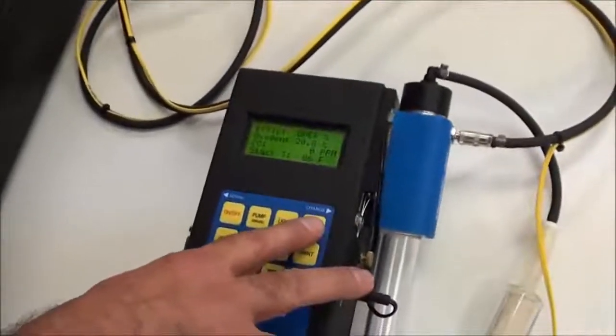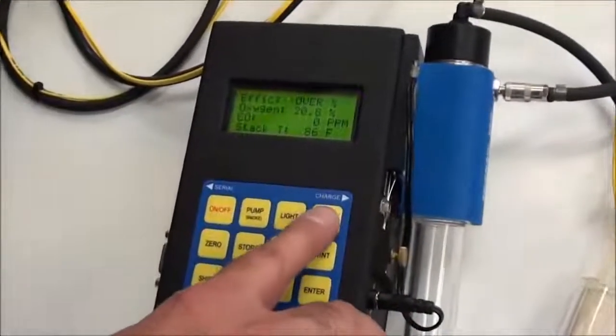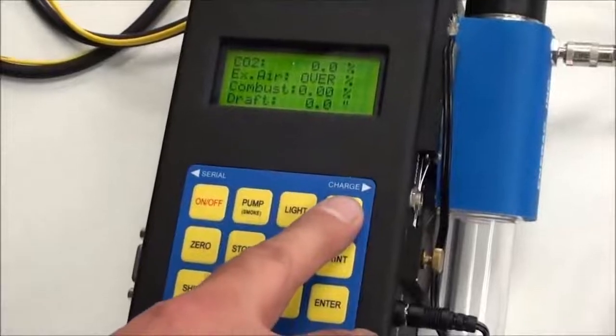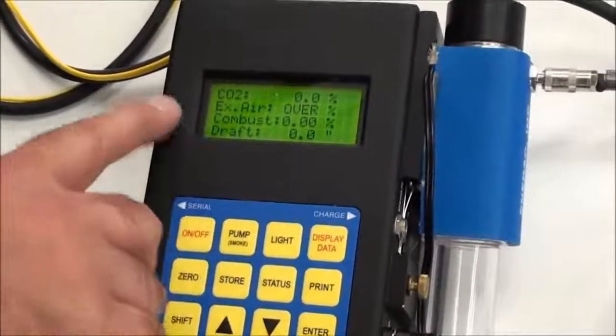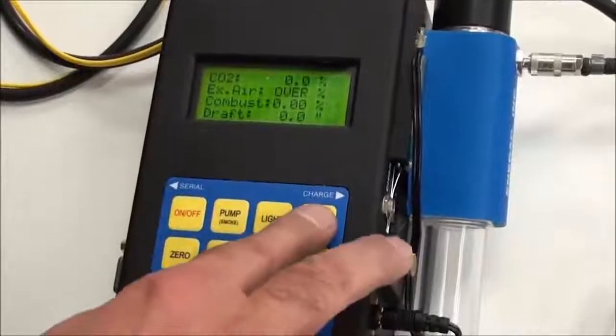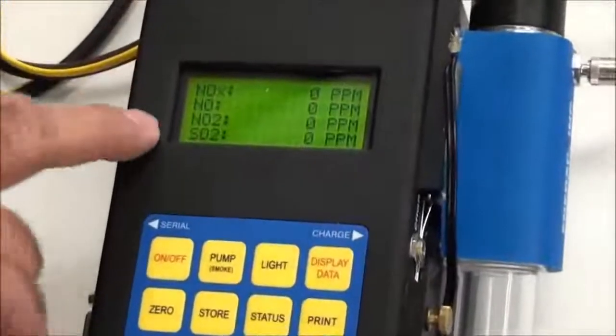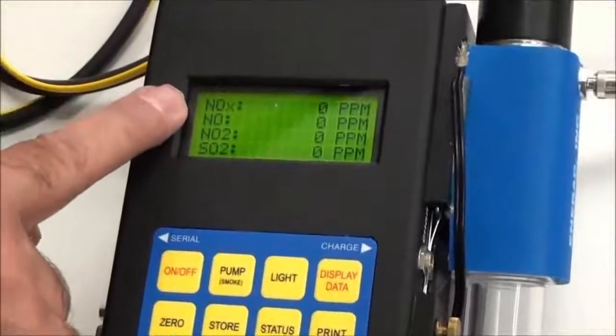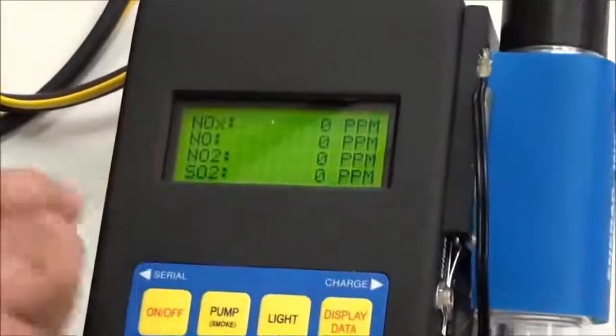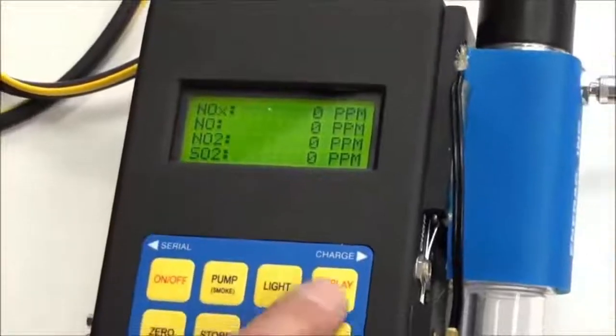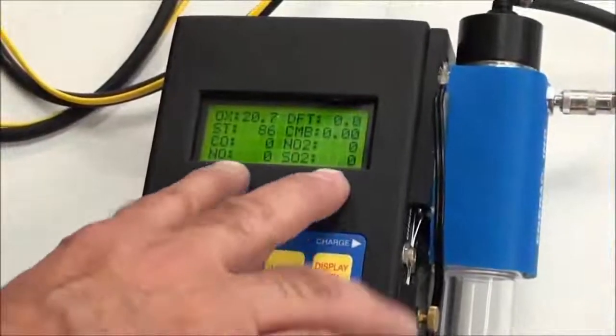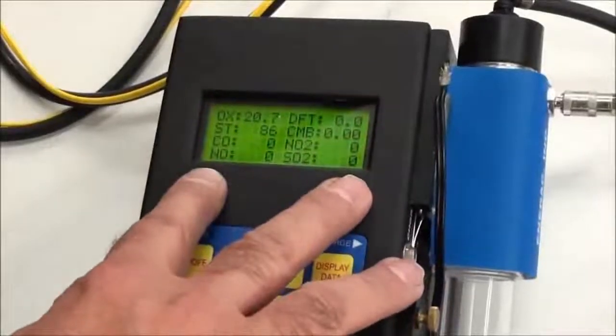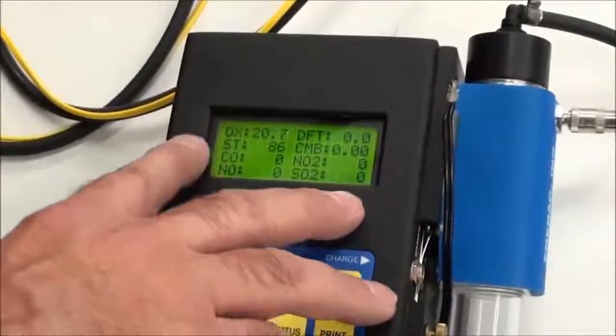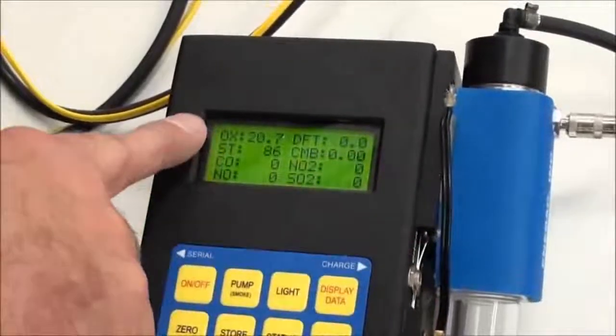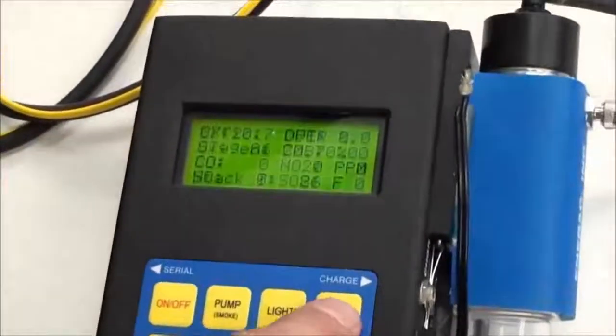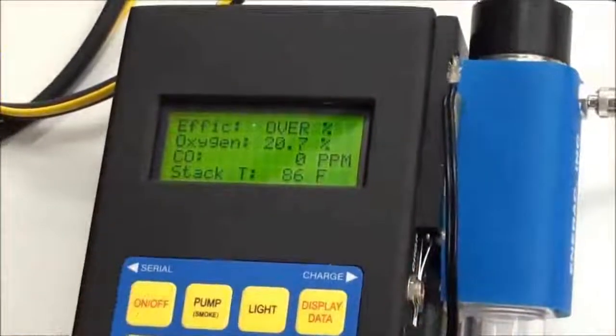Now what you'll do is you can check by simply hitting the display data button, and you toggle it through. You'll see on the second screen you've got your CO2, excess air, combustibles, and draft. Next screen, these are your toxic sensors. The NOx is a total of the NO plus the NO2, and then you have the SO2. And the last screen is just a compilation. It gives you all the readings on one screen that you might be interested in. Shows you your toxics, your stack temp, your combustibles, your draft, and your oxygen reading. And then you hit it again, it goes back to the beginning.